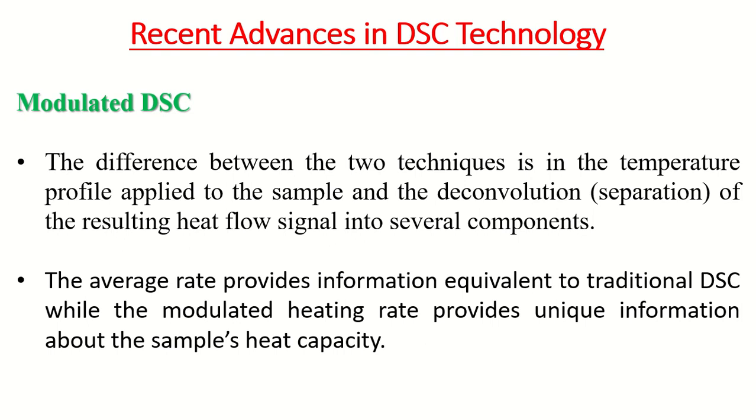The first one is modulated differential scanning calorimetry, modulated DSC. The modulated differential scanning calorimetry experiment can be performed on the same instrument as used for traditional differential scanning calorimetry measurements.